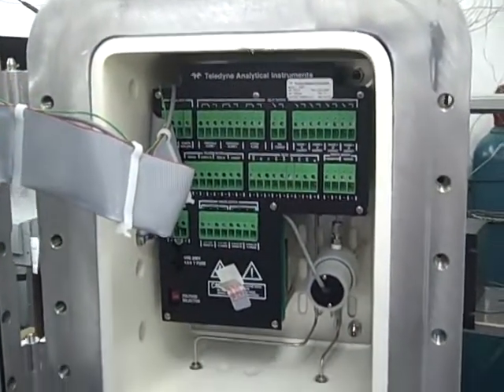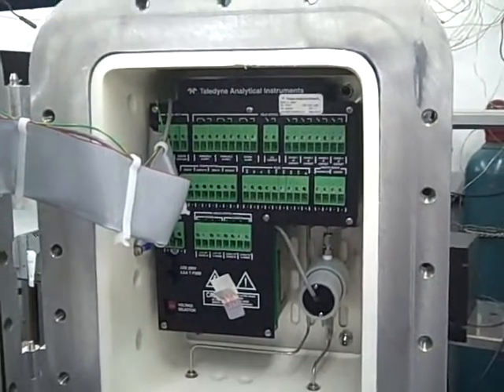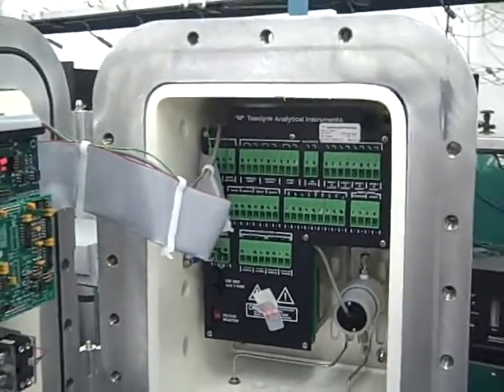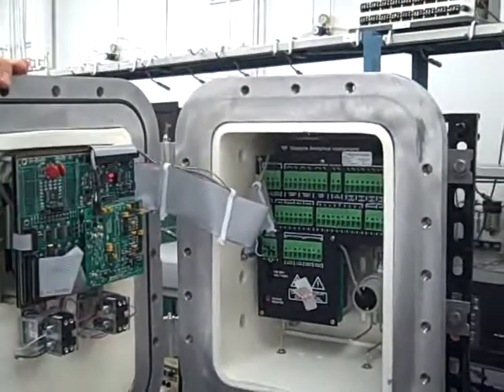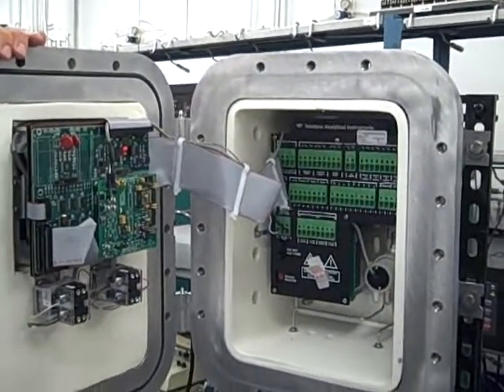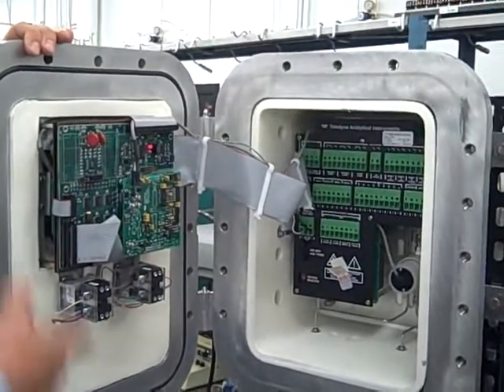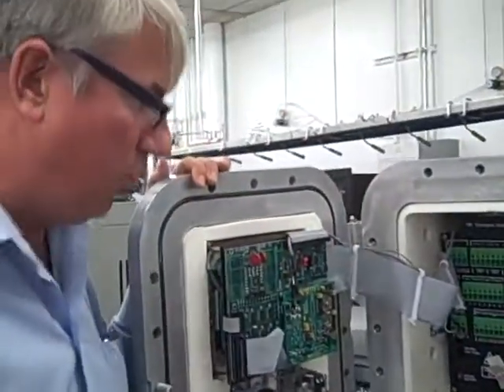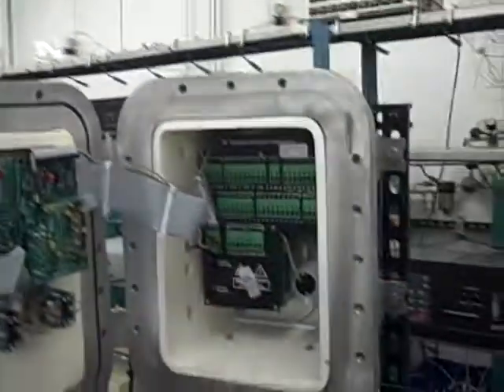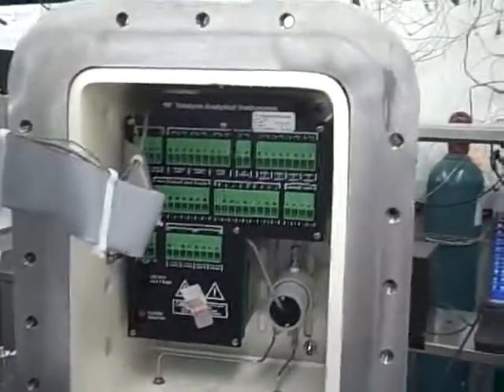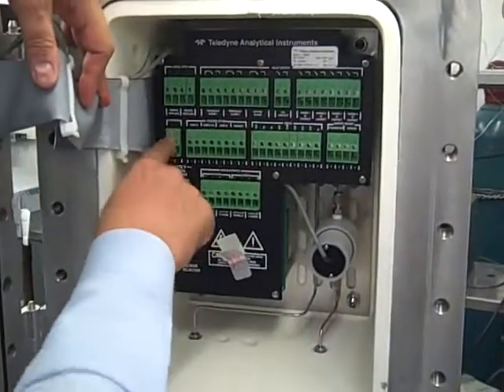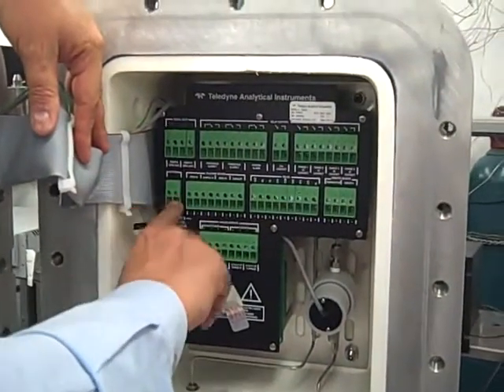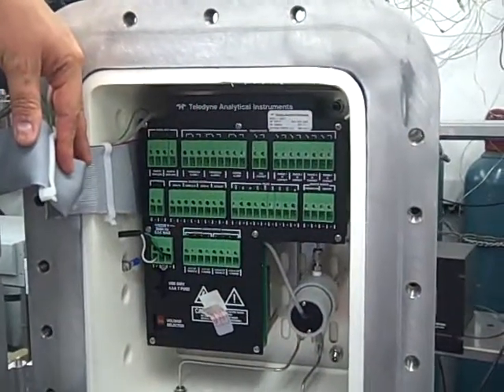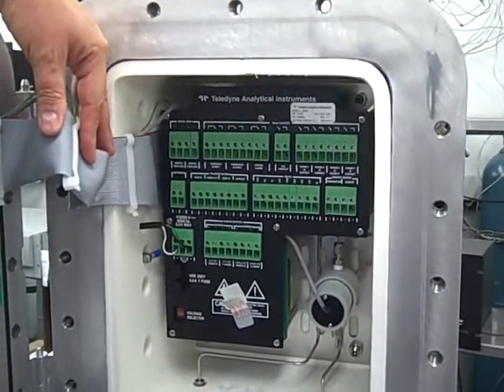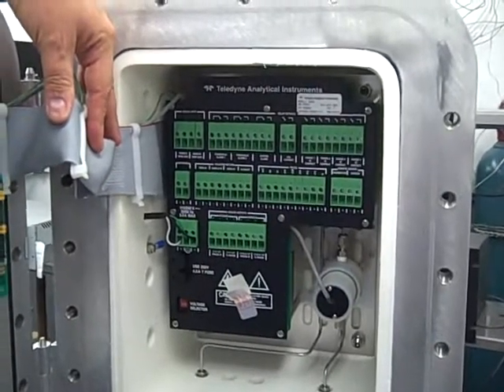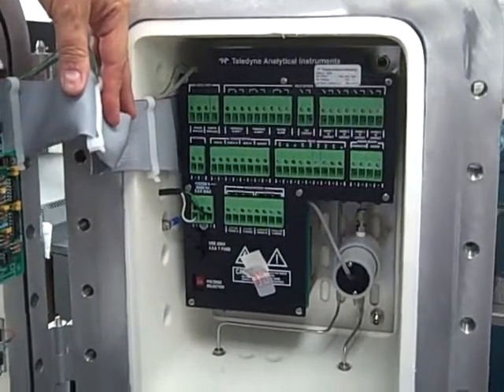This unit has 3 user programmable ranges. In this case, you can program any one of the 3 ranges to any range between 1 and 25%. So, for instance, you could set a range at 25%, another range at, say, 10%, and another range at 1%. You also have the range 4, which is a calibration range, which is always 25%. We have a network connection that's not used in this unit, so there will be no opportunity for network connection, but there is an RS-232 connection, which one can make a connection to if one wants to.